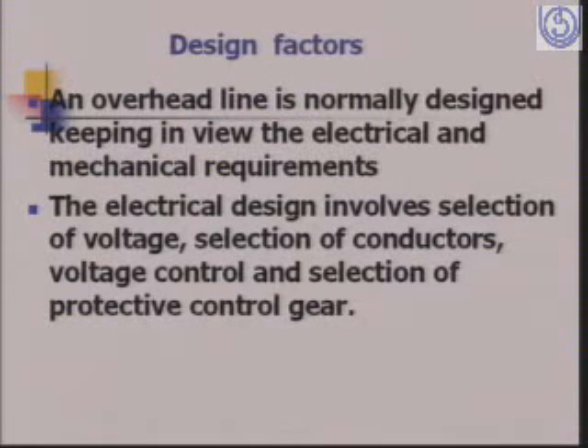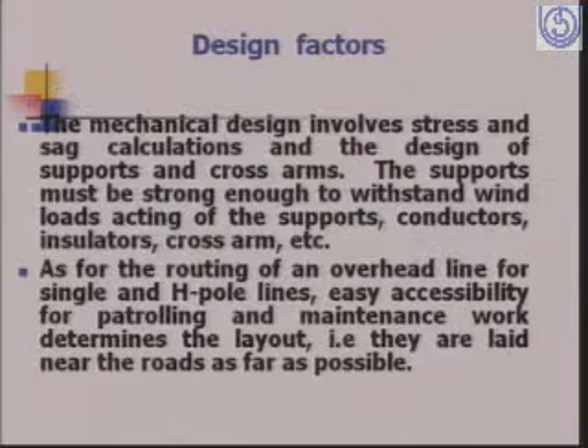So how is an overhead line designed? What are the factors considered for the design of an overhead line? An overhead line is normally designed keeping in view the electrical and mechanical requirements. The electrical design involves selection of voltage, selection of conductor, voltage control, and selection of the protective control gear. The mechanical design involves stress and sag calculations and the design of supports and cross arms. The supports must be strong enough to withstand wind, loads acting on the supports, conductors, insulators, and cross arms, etc.